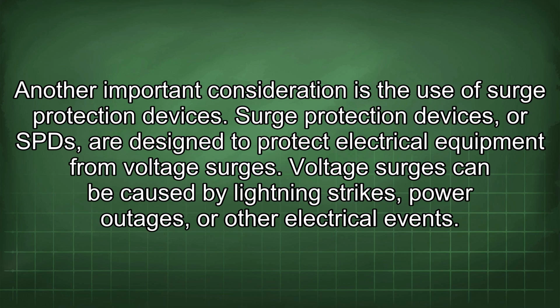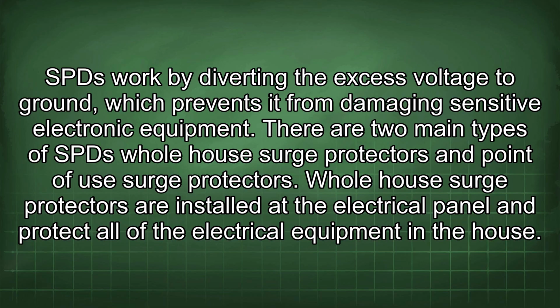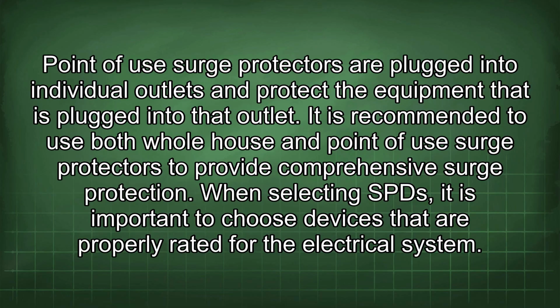Voltage surges can be caused by lightning strikes, power outages, or other electrical events. SPDs work by diverting the excess voltage to ground, which prevents it from damaging sensitive electronic equipment. There are two main types of SPD: whole house surge protectors and point-of-use surge protectors. Whole house surge protectors are installed at the electrical panel and protect all of the electrical equipment in the house. Point-of-view surge protectors are plugged into individual outlets and protect the equipment that is plugged into that outlet. It is recommended to use both whole house and point-of-use surge protectors to provide comprehensive surge protection.